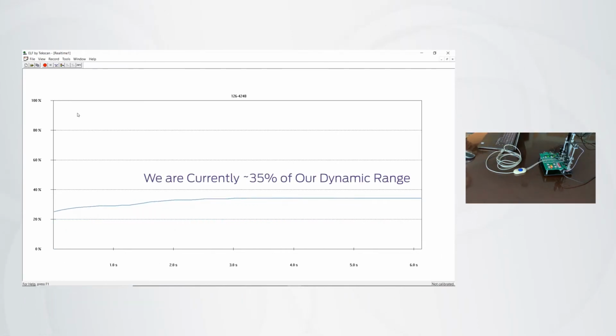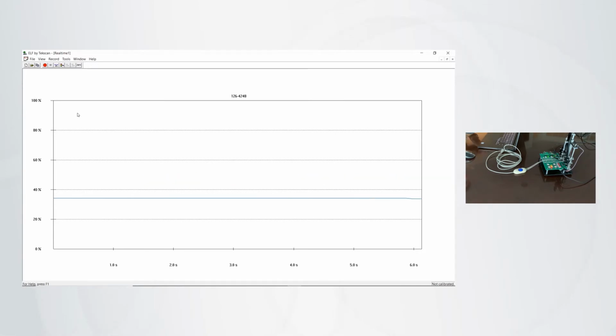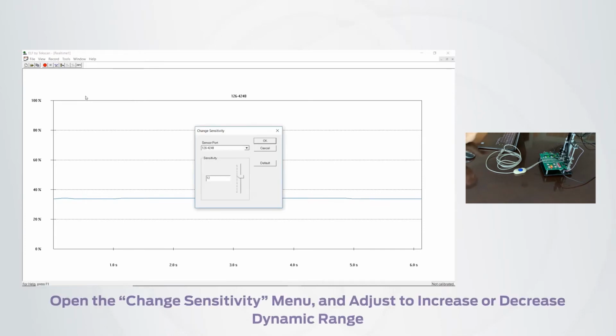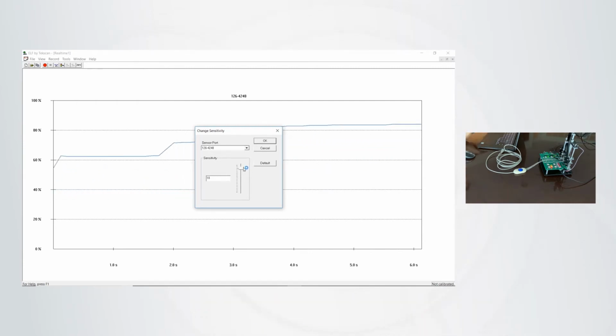And at 5 pounds, you're seeing that we're getting about 35% output. Again, if we were to continue to calibration or right to measurement this way, our lower load 1 pound and 2 pound range would be in the noise of the electronics. So what we want to do is open up our sensitivity adjustment dialog. And in this case, since the output is lower than we would like, we want to increase the sensitivity. So as you can see, we are aiming for about 80%, 85% at maximum load, and I think that looks pretty good.